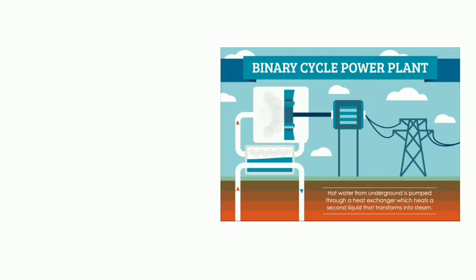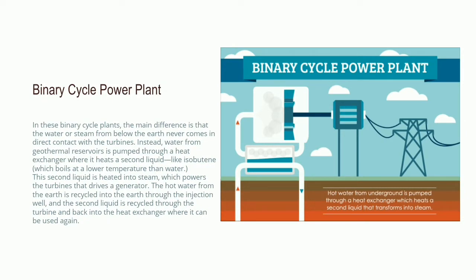In a binary cycle power plant, water is used at a lower temperature of approximately 225 to 360 degrees Fahrenheit. Using a heat exchanger and a secondary liquid, the turbine is turned to power the generator. In binary cycle, secondary liquids like ammonia, isobutane, etc. can be used, which have a low boiling point. The secondary liquid is maintained in a low-pressure reservoir. The heat exchanger supplies geothermal heat to the secondary liquid; due to the low pressure, the secondary liquid boils quickly and is converted into vapour, which is used to run the turbine and generator.